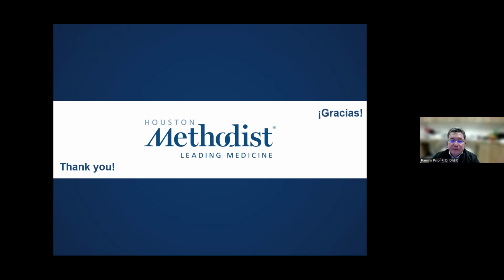Okay. Next question had to do with CatPhan. If you have any preference between CatPhan 501, 601, or 701, if you would recommend one over the other? We typically use the 601, but you would have to look at specifically what you want to measure, and whether it meets the requirements of your quality assurance program. So you want to look at your spatial resolution, integrity, Hounsfield units, and so on and so forth.